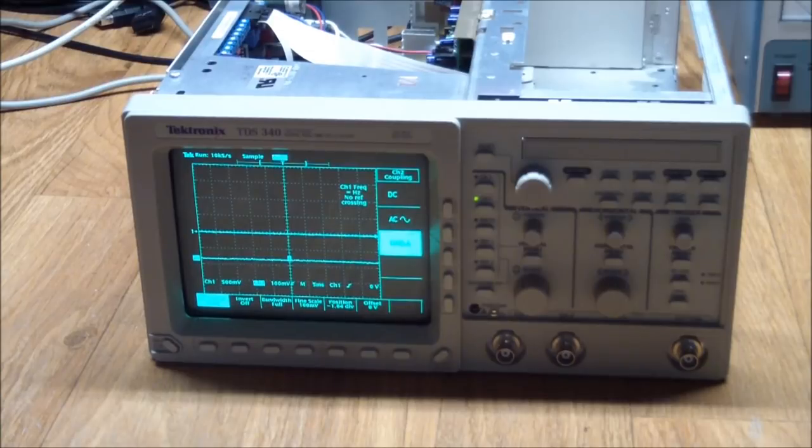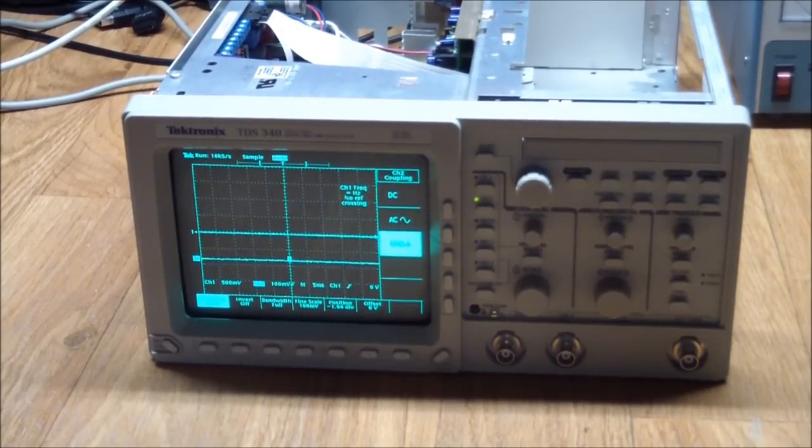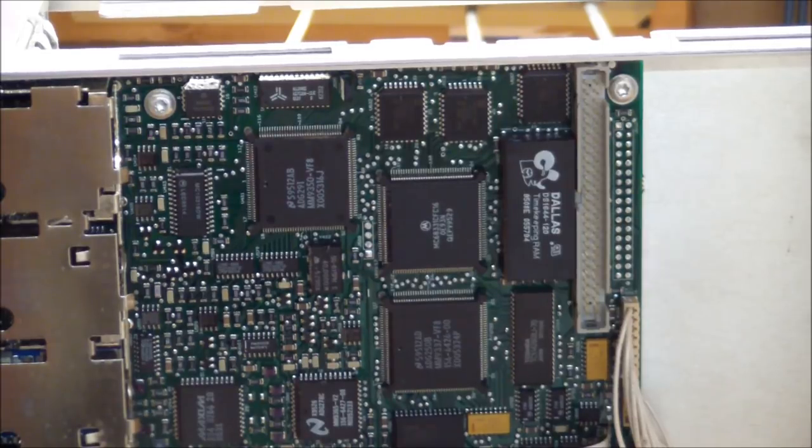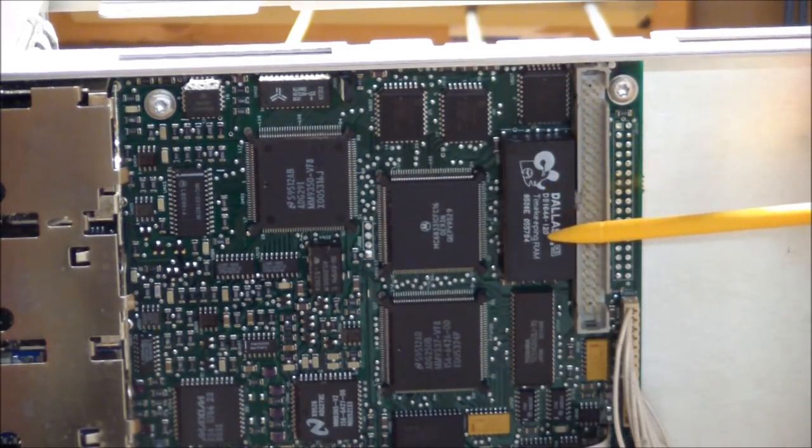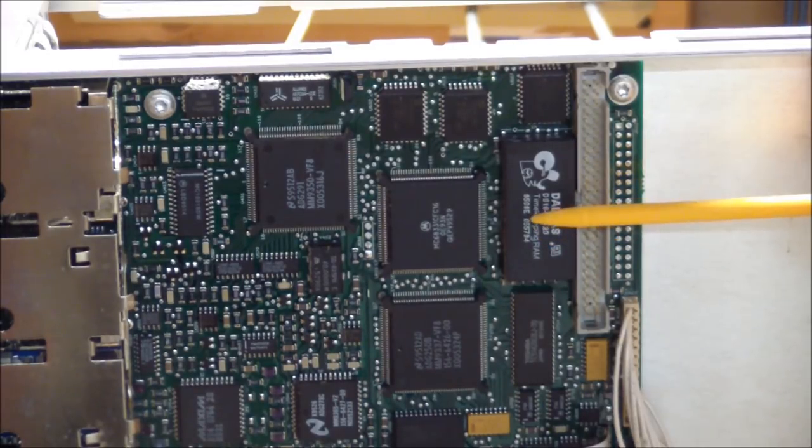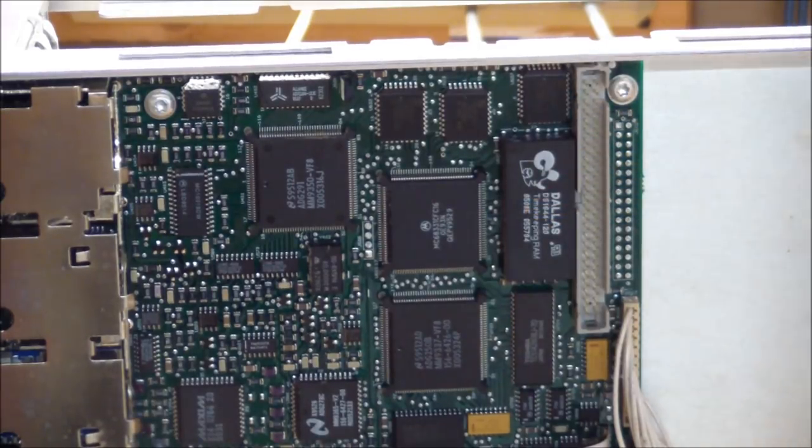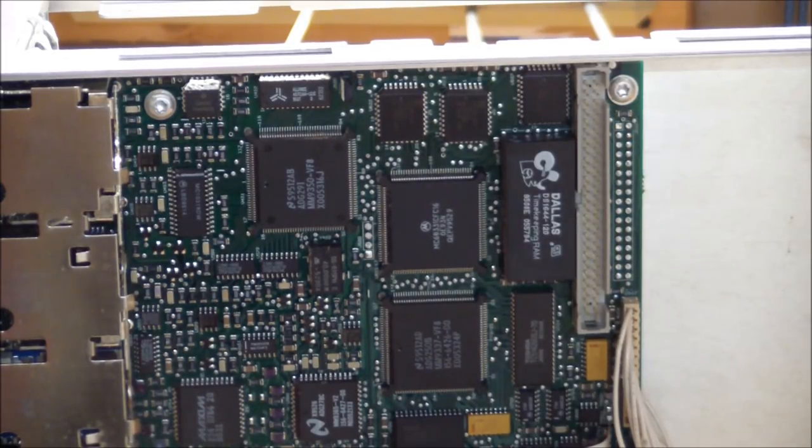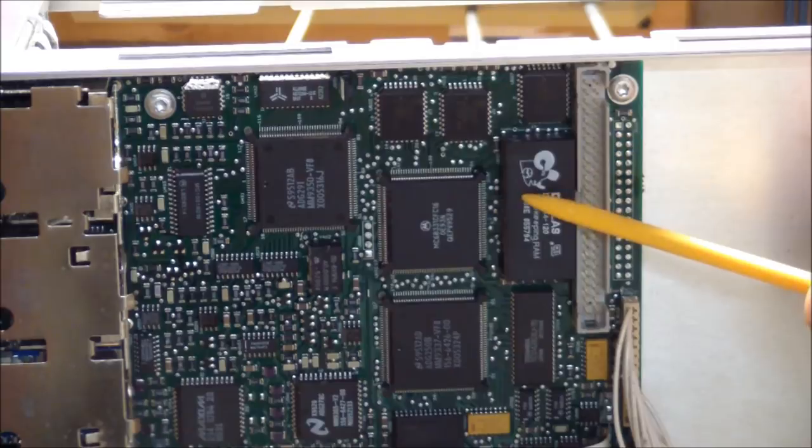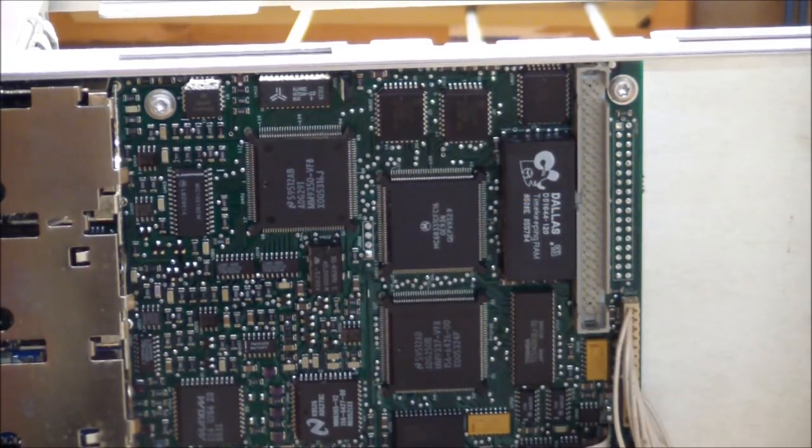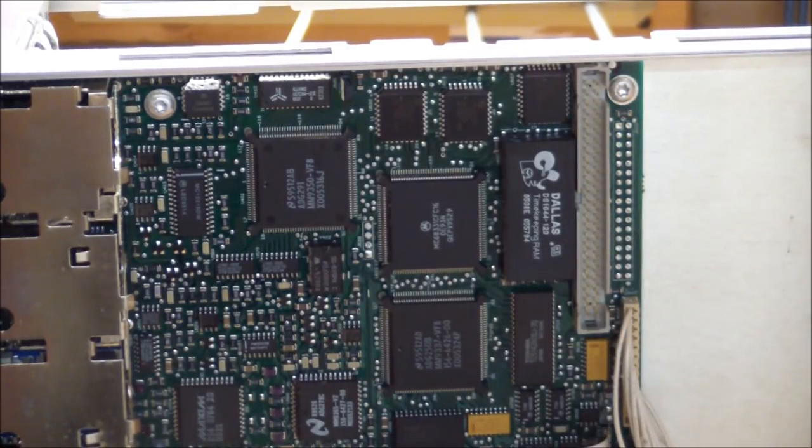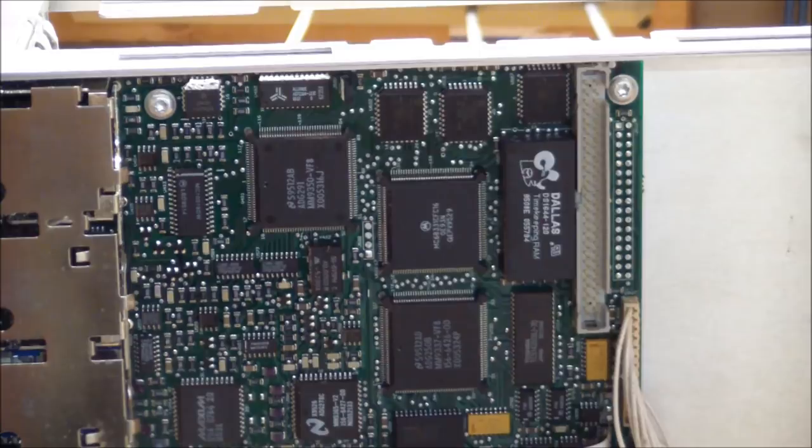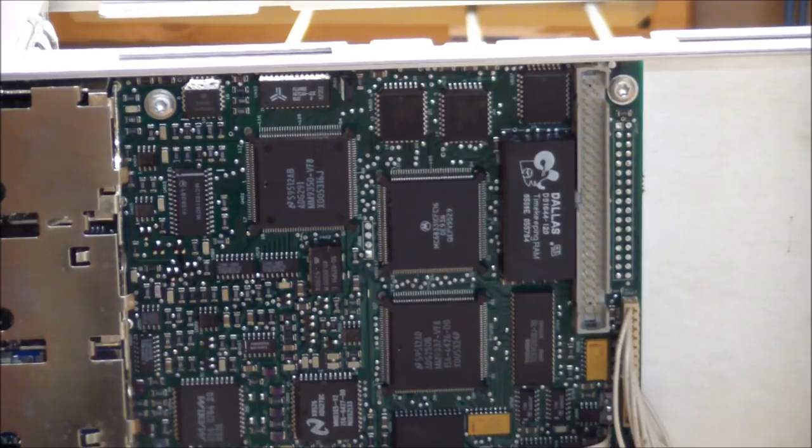Okay let me get a BNC cable, be right back. Now one thing I noticed that may be a problem here is it does have the battery-backed RAM and real-time clock module in here. And the battery is inside this package and it's not replaceable. Well not easily, anything can be done but I've looked into them and they're bonded inside. It's near impossible to change that battery, you have to get a new one. And I don't even know if this keeps all the calibration data in there and if it's live. And if it's not live, what do I have to go through to calibrate it. But well I guess we can turn it on and see if there's a way to display the clock and see what that says.